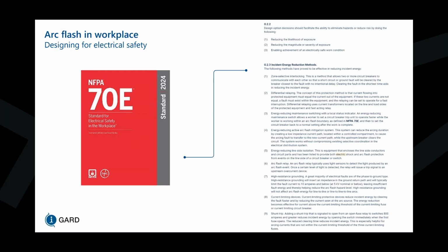NFPA 70E also has a mirroring standard in Canada, which is CSA Z462. This is a standard for electrical safety in the workplace. So basically, they're giving ideas to consultants on how they should reduce the likelihood and magnitude in Annex O.2.3, which lists out 9 different incident energy reduction methods. Of the 9 listed, we're going to be focusing on reducing the likelihood of exposure and reducing the magnitude or severity of exposure.